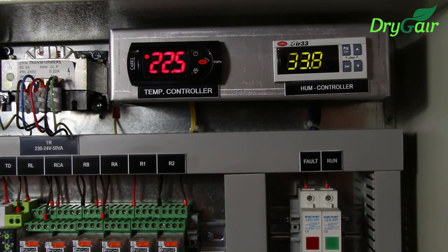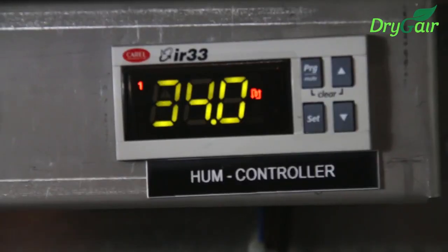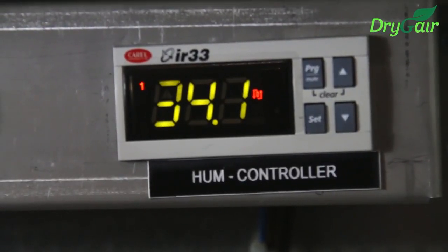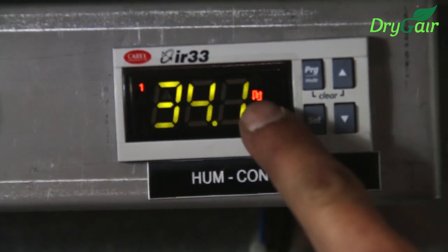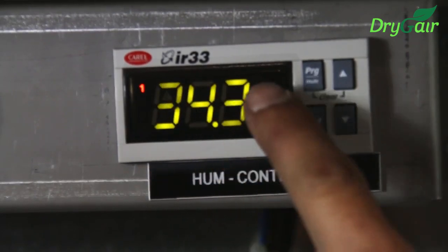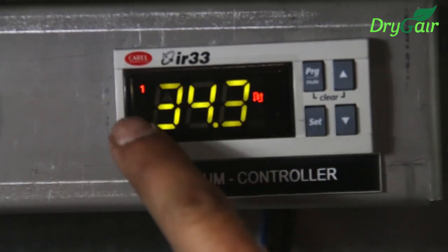When operating the unit remotely with the use of a climate control system, you should also set the humidity set point into the climate control system. The unit will work based on the set point dictated by the climate control settings. Notice the two orange lights that appear on the screen on both sides of the relative humidity percentage. When these lights are on, the DryGair is currently receiving a command to dehumidify.